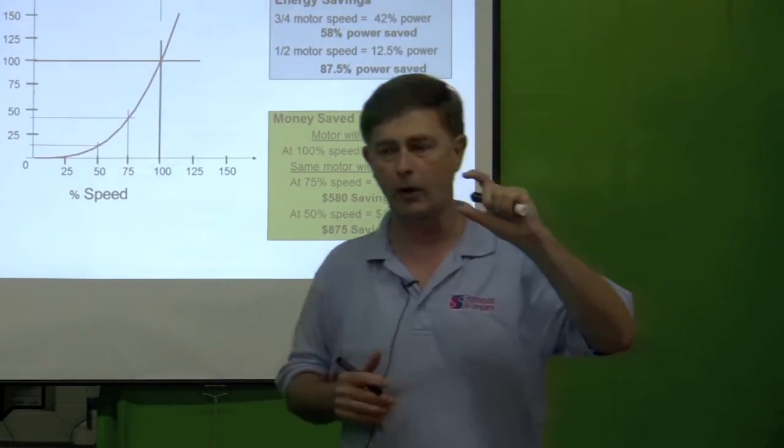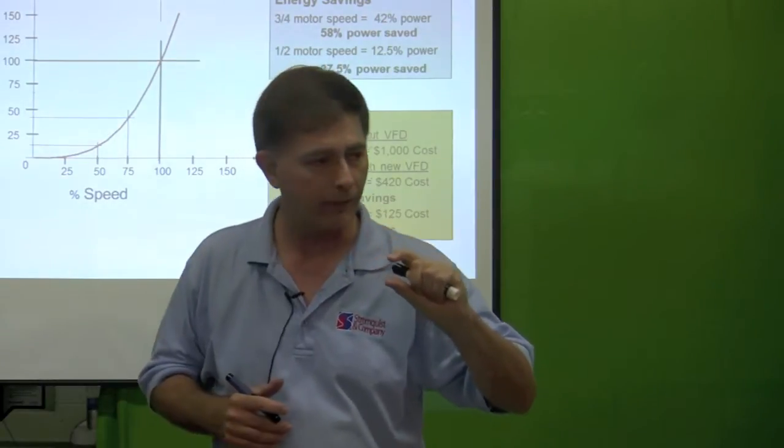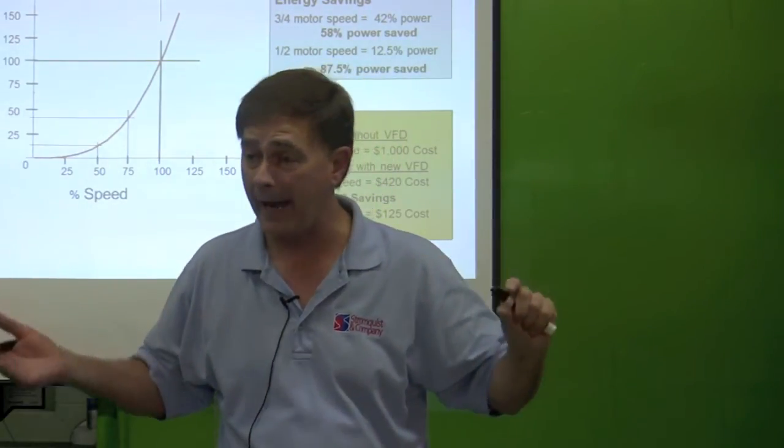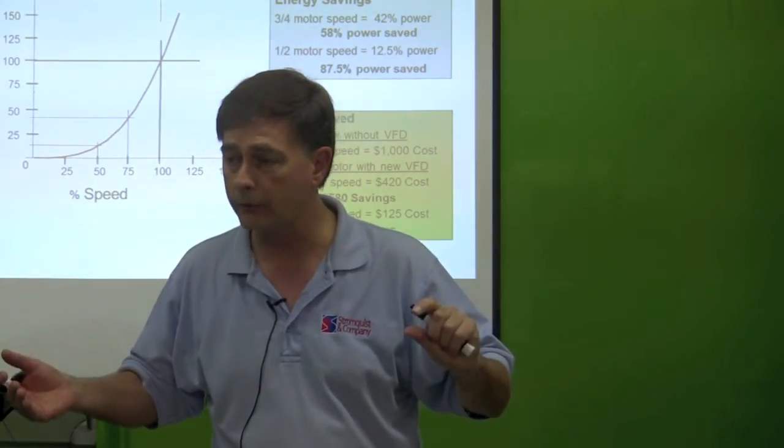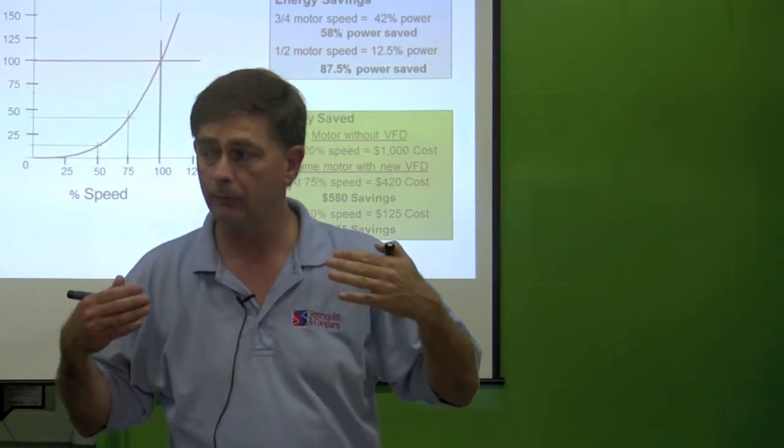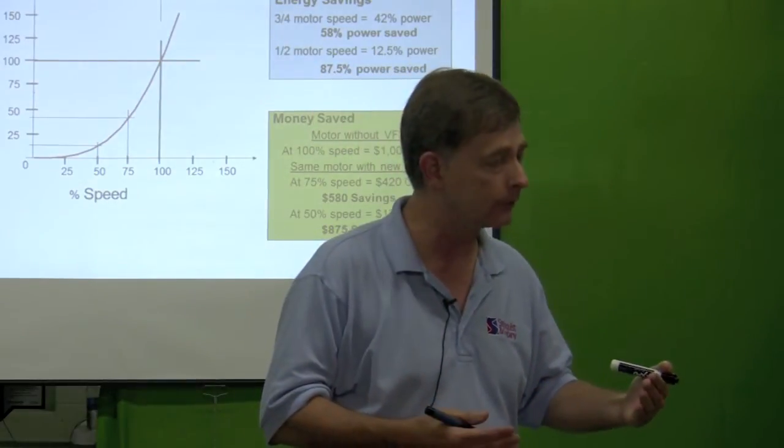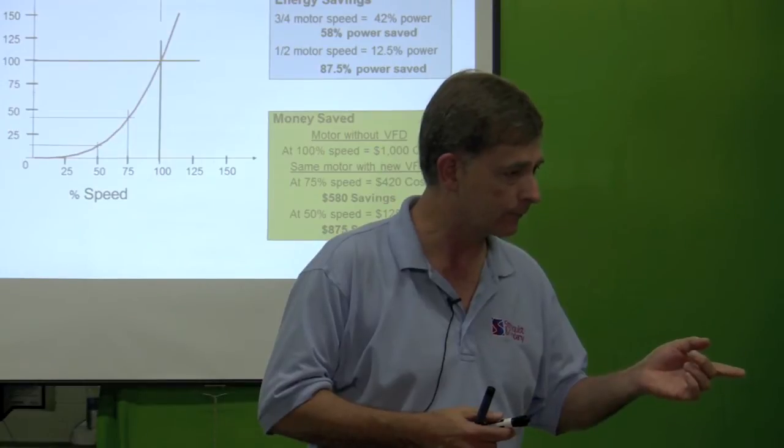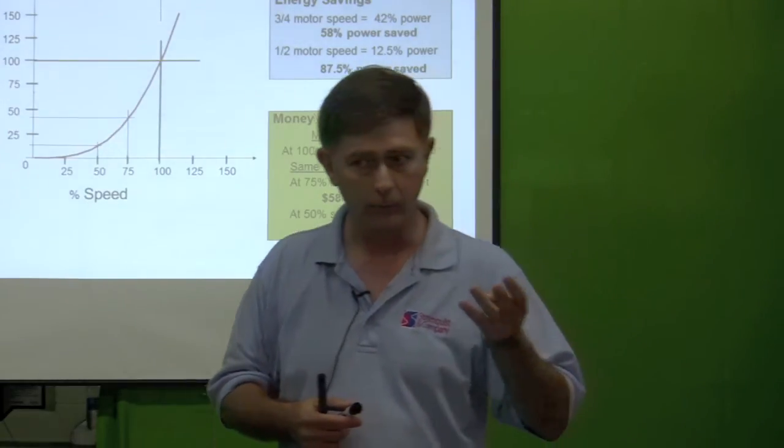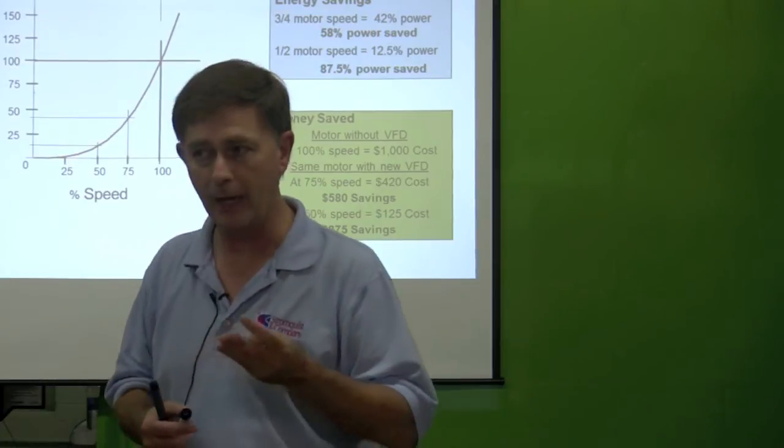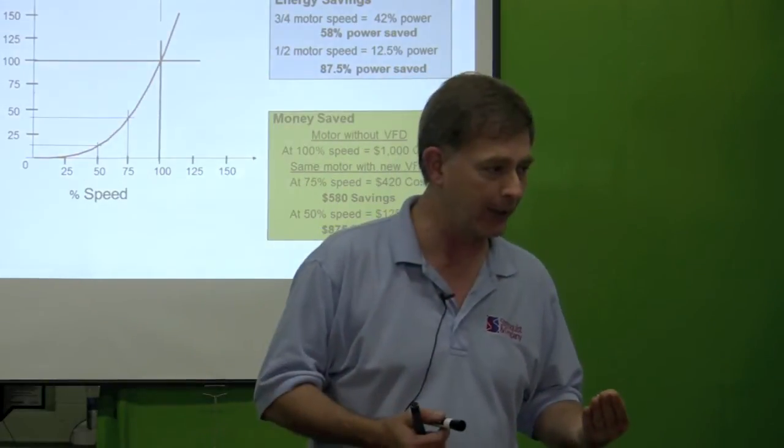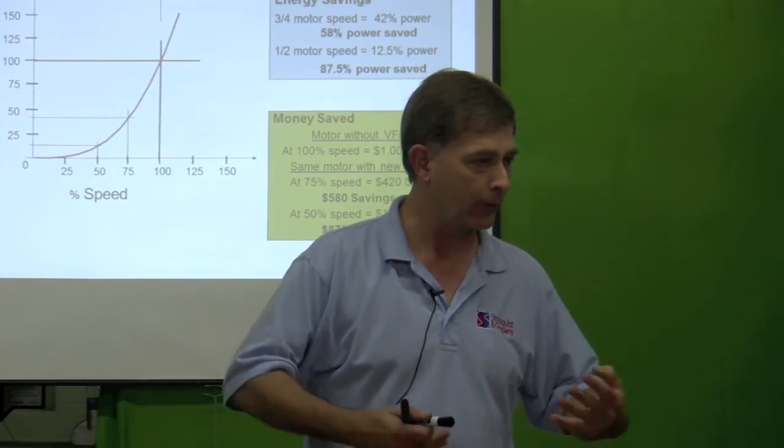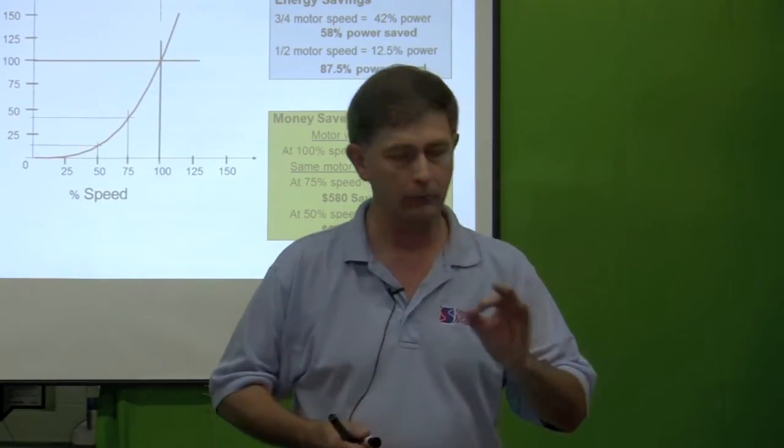Now, if you look up there, if you throttle it back 20% to 25%, you save half of the power that motor consumes. Most of our power that's generated is consumed by buildings, commercial buildings, moving water and air. And we've established that most of the time, we don't need all that water and air. So if you can throttle back now, for instance, 60 hertz is what a motor operates off.